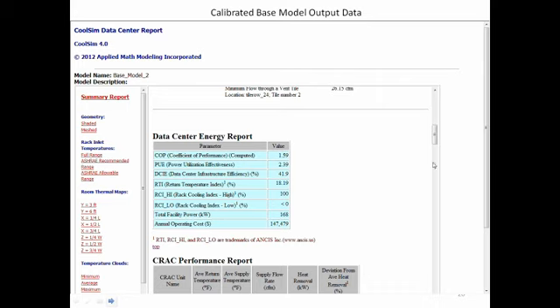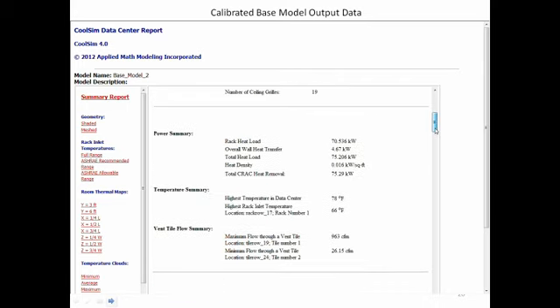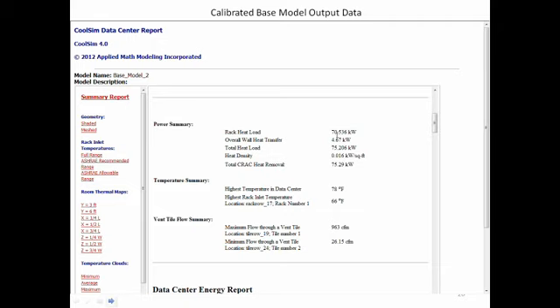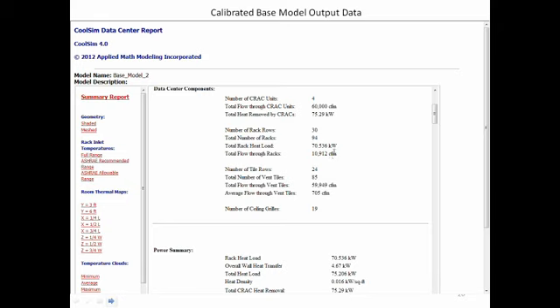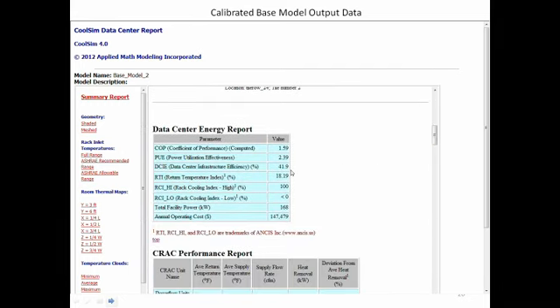Just awful. Now, the reason that's true is if you take a look up here, we only have 70 kW of load. We've got some heat being transferred into the room, because we're running the room at 55 degrees. So we're cooling adjacent spaces. So we've got a total heat load of 75 kW. So normally that would want a total of 10,000 CFM, at least the 70 kW would. It'd want 10,000 CFM. But we're generating 60,000 CFM. So we're off here by a factor of 6. And that's what's driving this number so low.